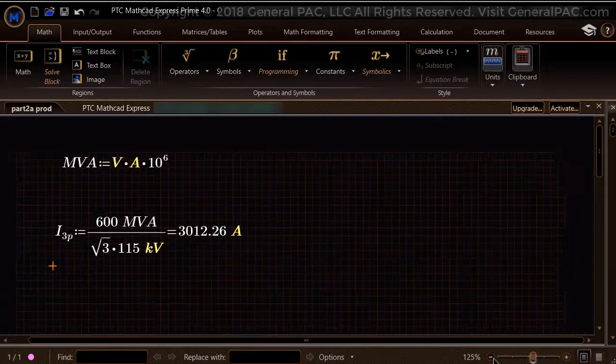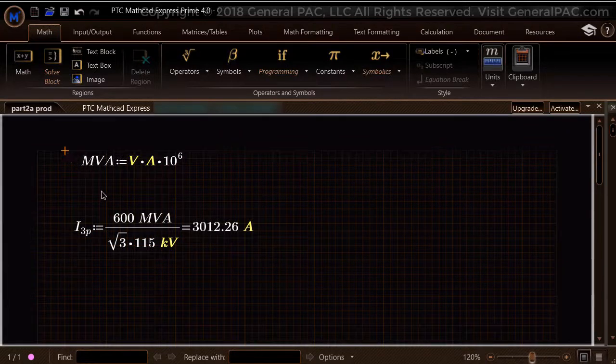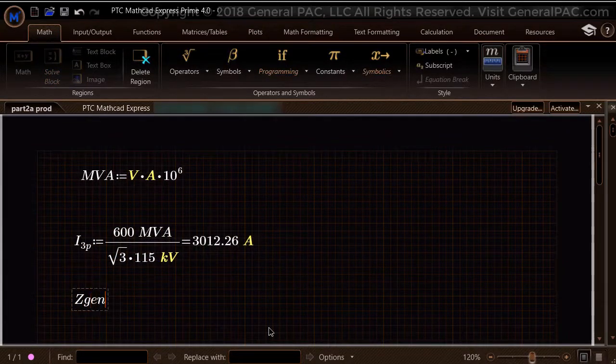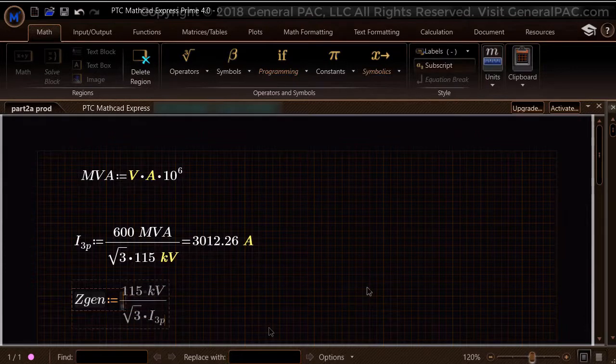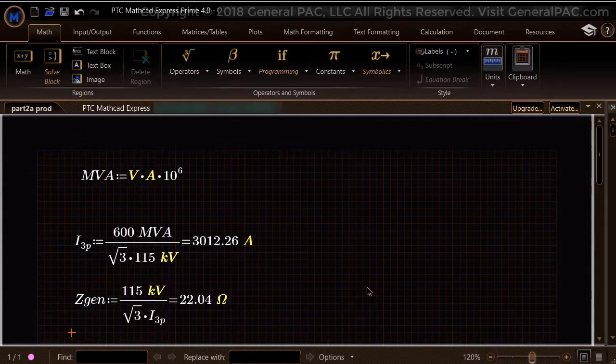We can now calculate the impedance value by dividing the voltage over the current, times the square root of 3. The square root of 3 must be accounted for because it converts the voltage to a line to ground quantity from the given 115 kV line to line quantity. The impedance value is calculated as 22.04 ohms.